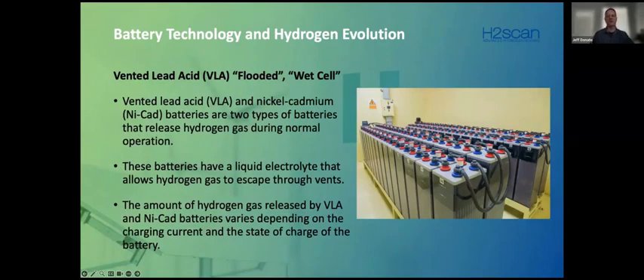We also call them flooded or wet cells. These vented lead acids you might call lead antimony or lead calcium batteries. Typically, they're lead calcium in substations. We also have another vented type, which are NiCads. Instead of a sulfuric acid and water electrolyte, you'll have potassium hydroxide. But in either case, electrolysis does occur, and they both will vent hydrogen.